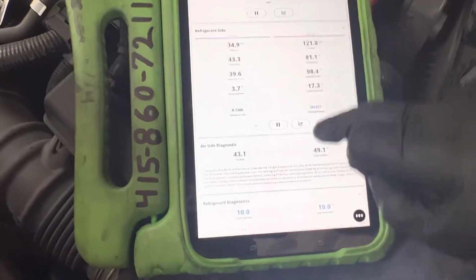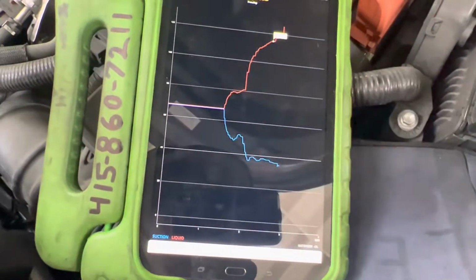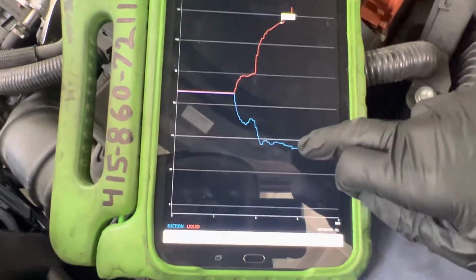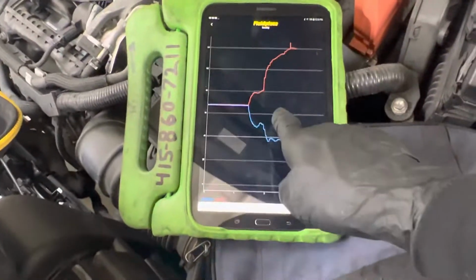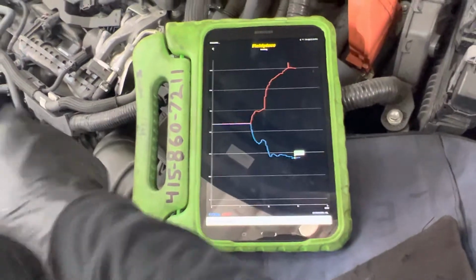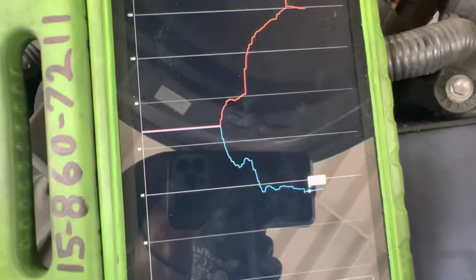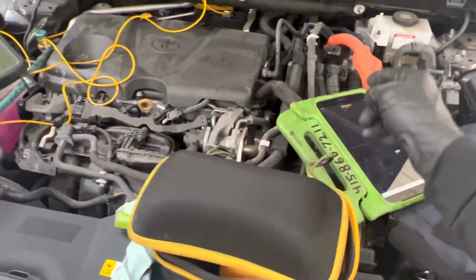Let's go back to pressures. The low. So that'll be a snapshot of the startup profile of this electric high-speed 3-phase high voltage compressor. All right, that's it for now. And of course, you data log this, you record it, you snapshot it, and you include it on your customer's receipt.